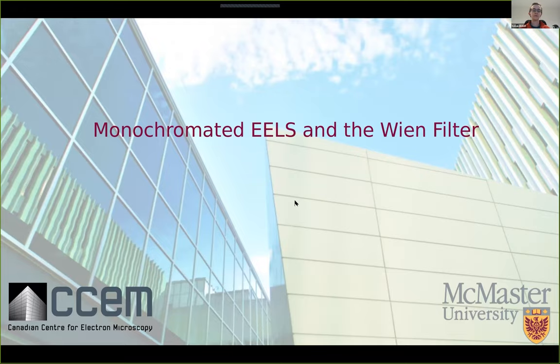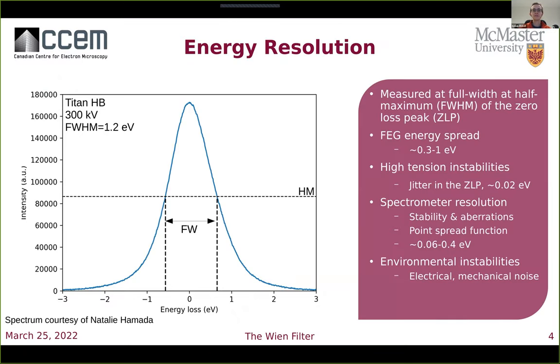Monochromation is very interesting for EELS because using a monochromator you're able to improve the energy resolution of your spectrum. If I take an EELS spectrum and look at the zero loss peak — electrons which have not lost any significant amount of energy to the sample — and look at the full width at half maximum, I use this as a measure of the energy resolution. The unmonochromated zero loss peak can have an energy resolution on the order of a few hundred meV to an eV.